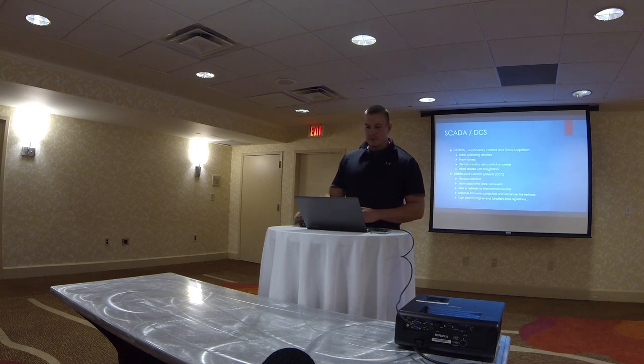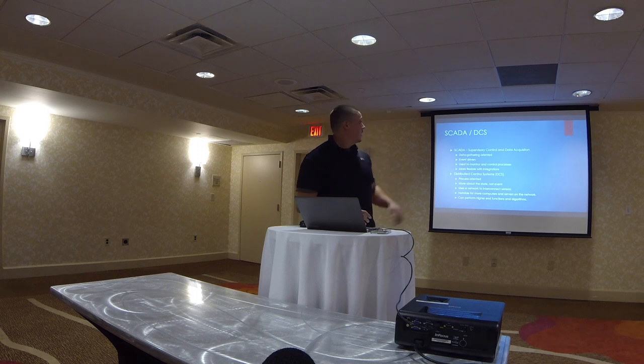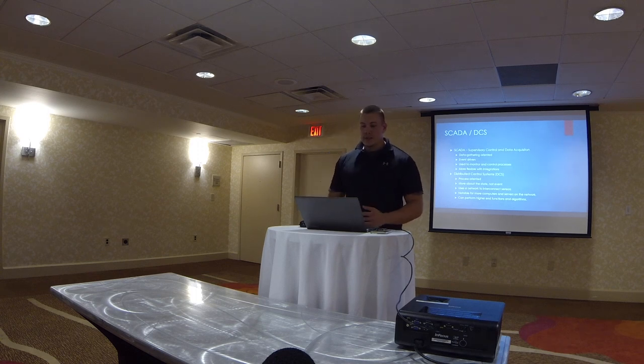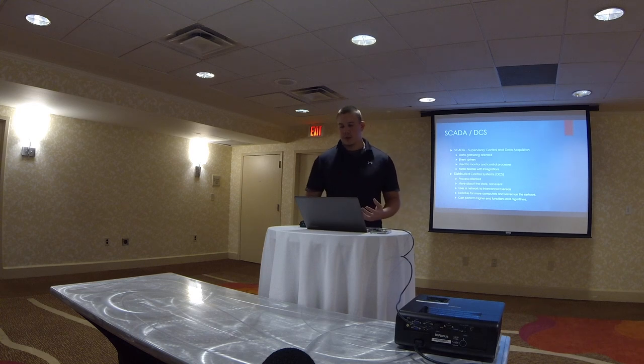So I'm going to dive down a little bit into the difference between SCADA and DCS. SCADA is the key ability to perform a supervisory control action or operation over a variety of proprietary devices - a bunch of actuators, something that sends a signal to the SCADA device. It's what it's looking for.